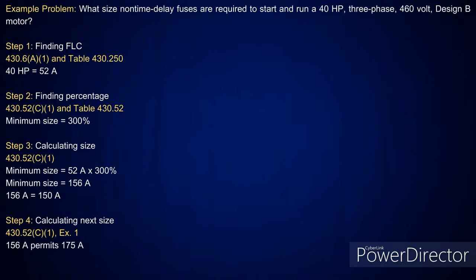Now, without doing anything further, I can look at exception one and just go up to the next standard size if it fails to start due to the inrush current, which in that case would be a 175 amp overcurrent device. Okay?